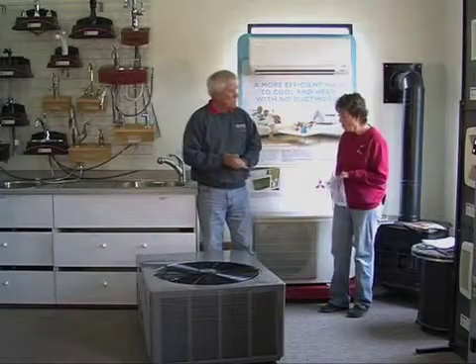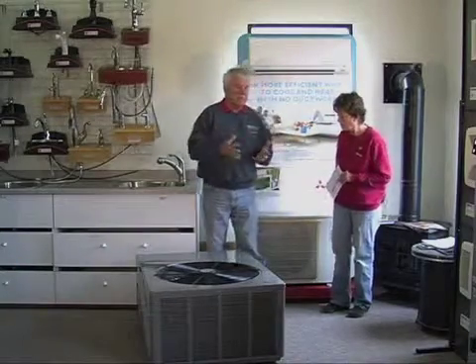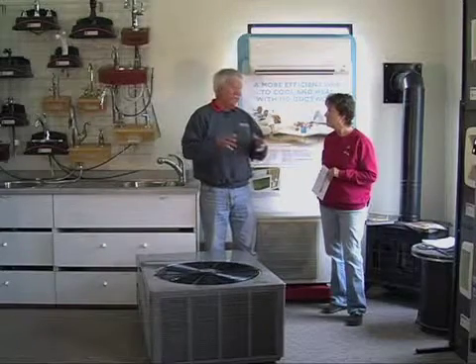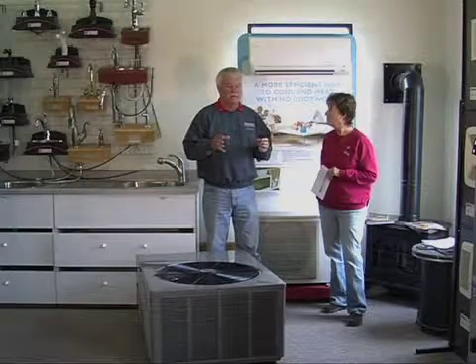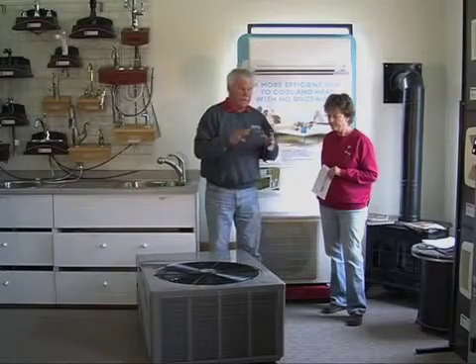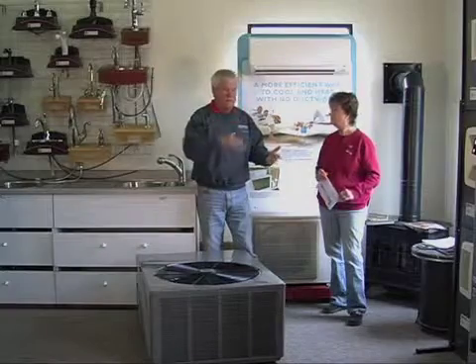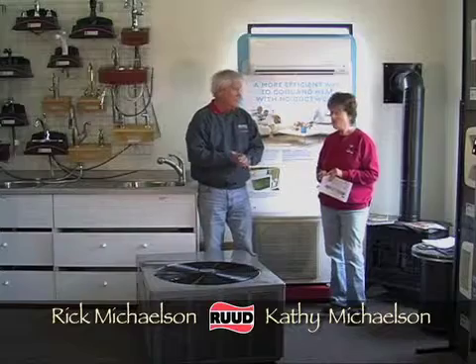Right. So then we'll quickly talk a little bit about energy efficiency and the fact that you might pay X amount of dollars for a system, but there's rebates available. That's right. Right now, this year is similar to last year, where the minimum efficiency is a 13 SEER. Air conditioners are rated on a SEER rating, which means seasonal energy efficiency rating. And the 13 SEER is the basic one, that's kind of the baseline, and then it goes up to 14 to 15. When we get into these ductless units, we're well over 20. Okay. So they're very efficient.